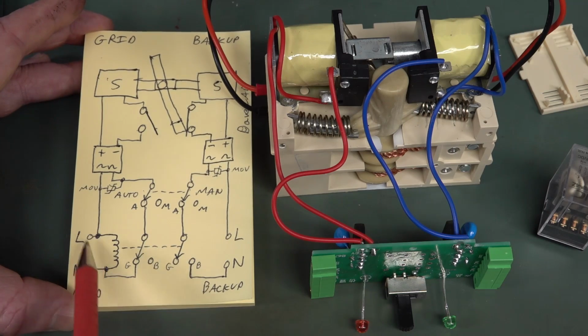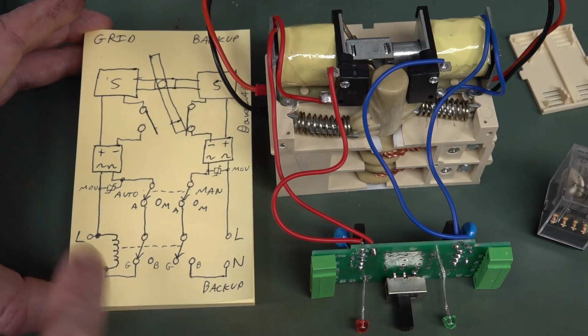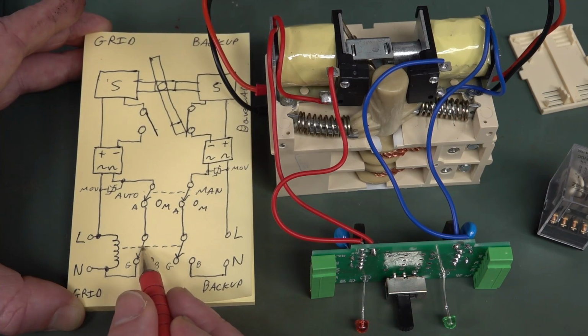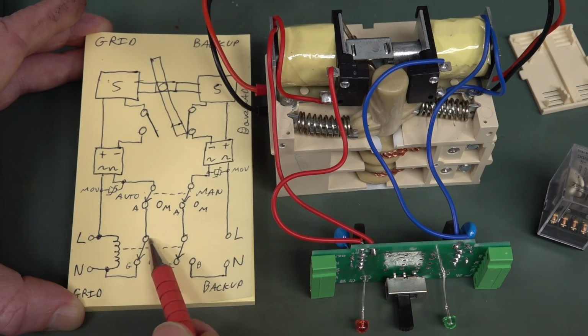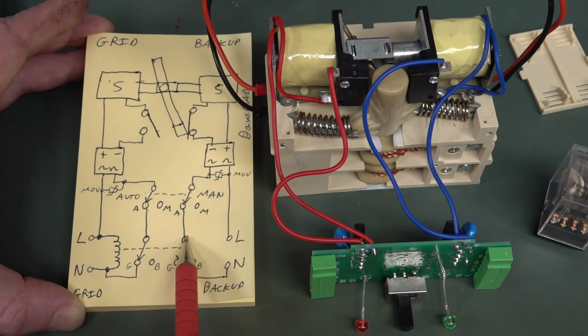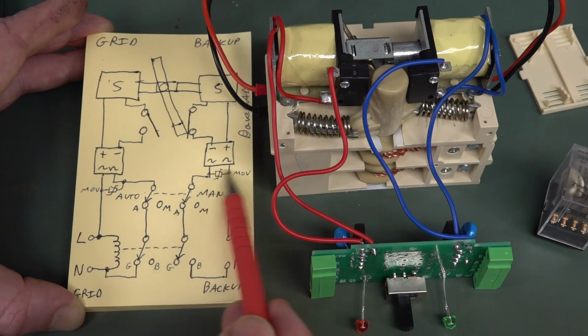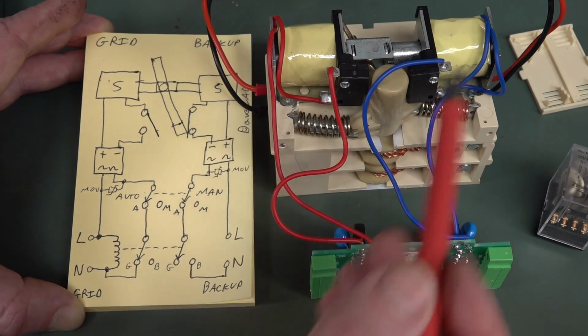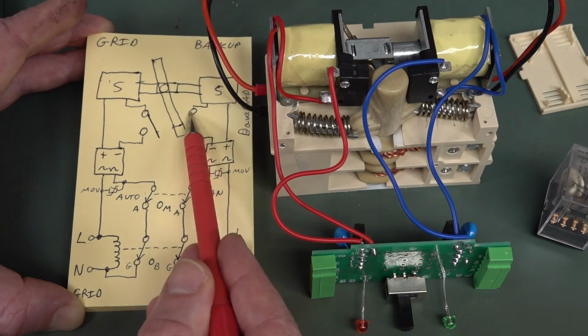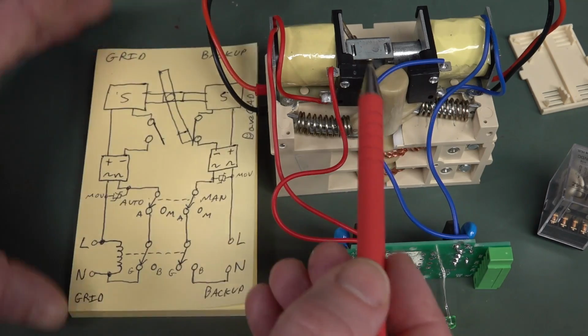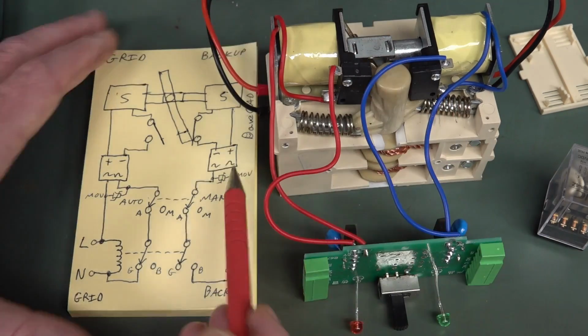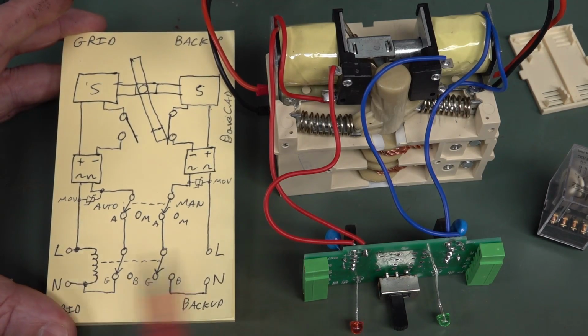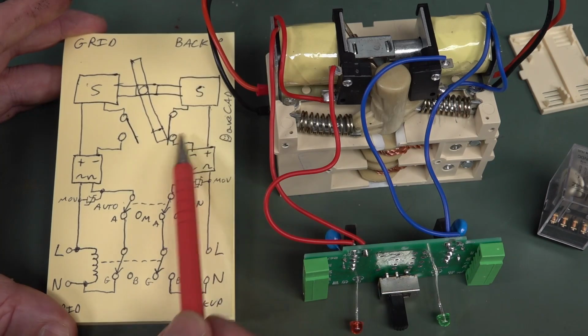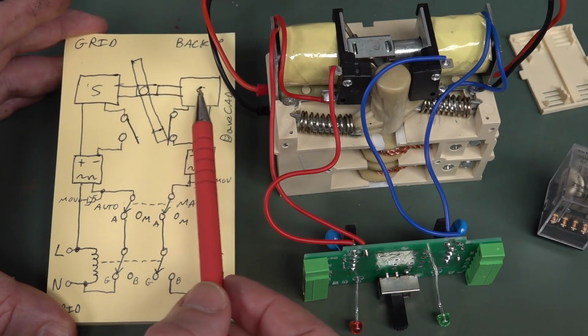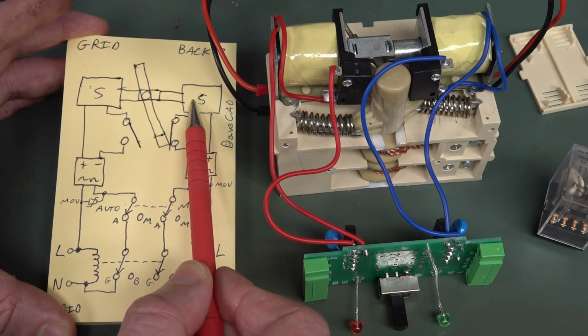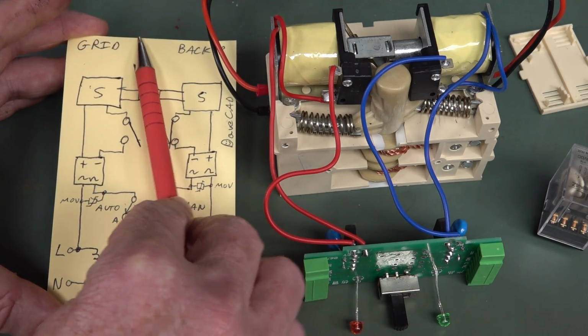So what happens if the grid, the main priority power source, fails? You remove the power from here, well, the relay suddenly de-energizes and switches back over to here. What that does is instantly apply power to the diode bridge for the backup side here, and because this micro switch is physically closed by this lever in this position, okay, as soon as this power fails, this diode bridge is going to get power, and this micro switch is closed, and this solenoid is going to activate, and it's going to go ka-clunk and pull this armature from here over to here.